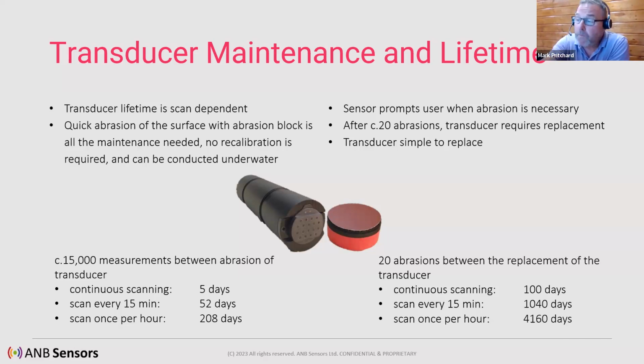Very simple to do. Replacement of the transducer is under 3 minutes. As Nathan just mentioned, it can be done by the user. No special tools required. There's 2 cross-headed screws that you need to remove, pop out the collar on the transducer, prise out the transducer, and pop a new one in, and it's good to go.